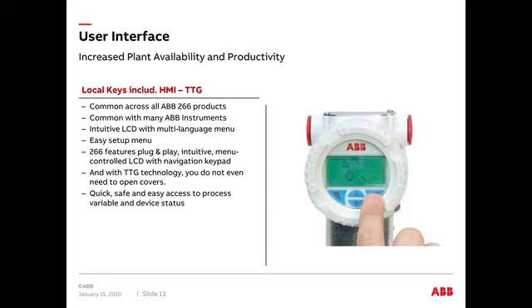With ABB, you have through-the-glass technology as possible. So if you're in an environment where you don't want to open that pressure transmitter up, you don't need to - you can go right through the glass, and you don't need a hot work permit if you're in an explosive environment. So there's a good advantage with the through-the-glass technology - it offers quick, safe, easy access.